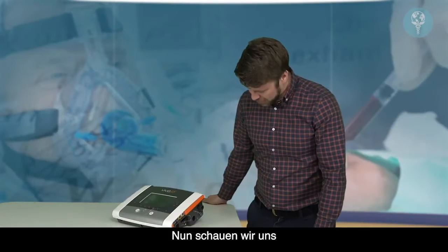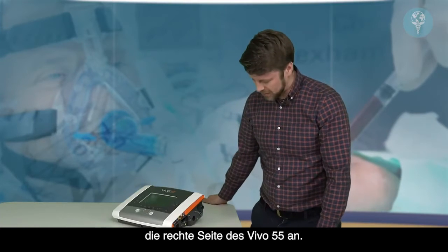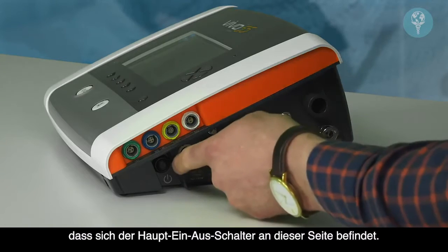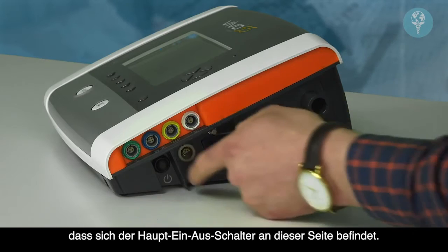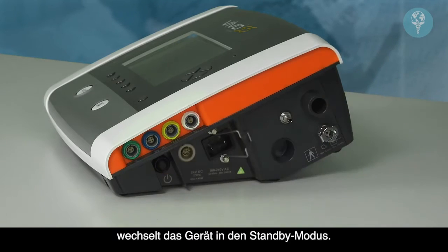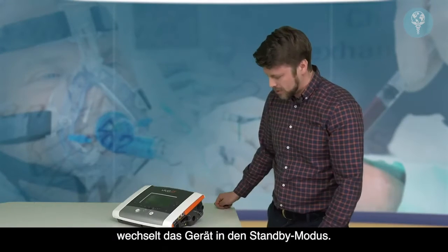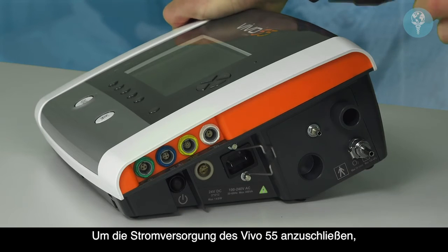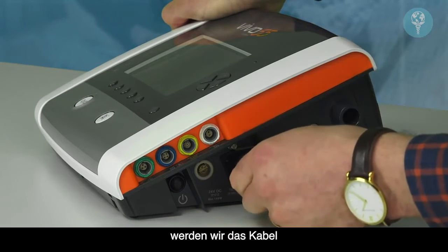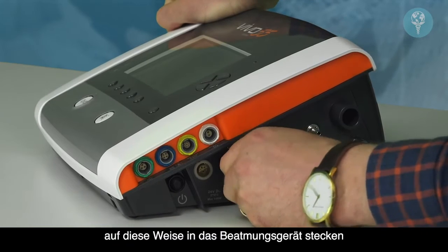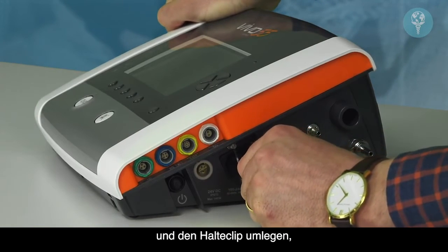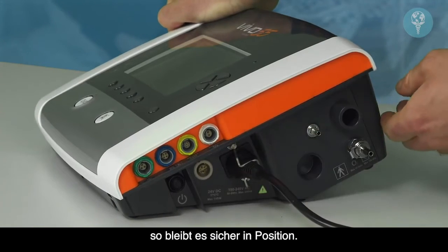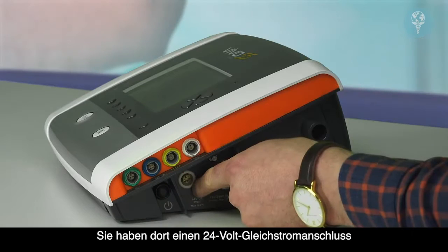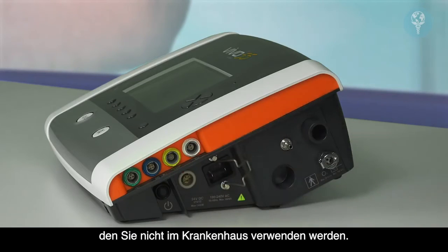At this time, we're just going to go through the right-hand side of the Vivo 55. So I just want to first point out the main on-off switch on the side there. If you press that button once, the device will come into its standby mode. To attach the mains power to the Vivo 55, we would just put the lead into the side of the ventilator, like so, and then we would bring the latch round so it's clipped safely into position. You have a 24-volt DC connection there, which you won't be using in the hospital environment.